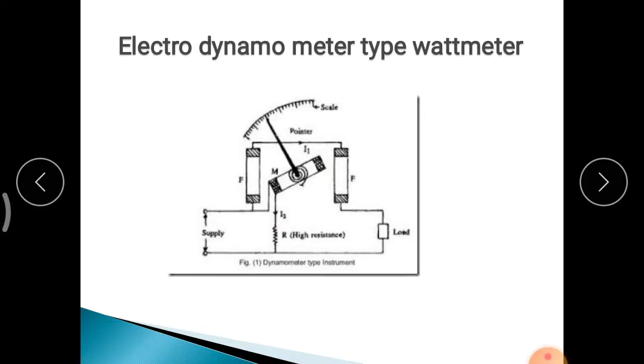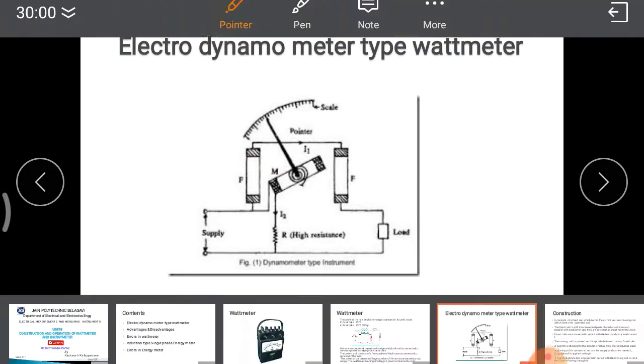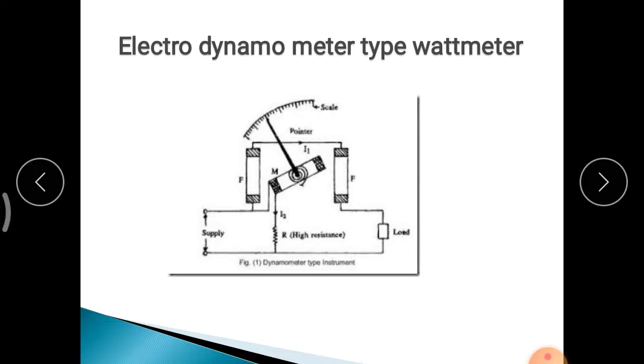The Electro-Dynamometer type Watt Meter consists of two fixed coils and one moving coil. The two fixed coils are connected in series with the load, and the moving coil is connected in parallel with the supply. There is a pointer, a scale, and one resistance connected in series with the moving coil. Regarding construction: the fixed coil is split into two equal parts placed at a distance, parallel to each other. The fixed coil is the current coil, connected in series with the load, and carries current I1.